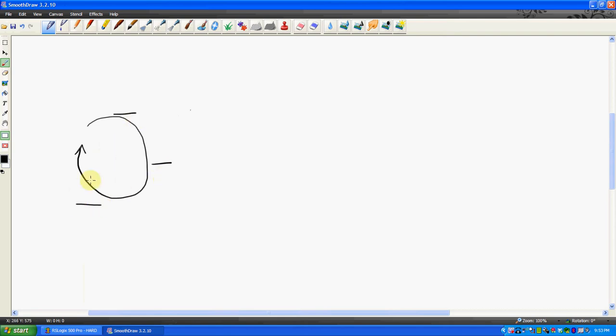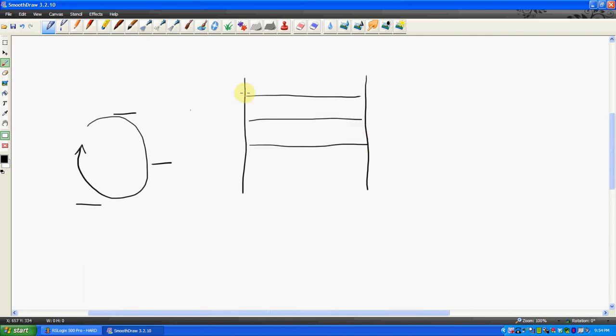It's sort of a bigger picture of what's happening in the whole PLC, but more to the important part of this video, ladder logic inside the PLC is always processed the same way. It's always processed the way we'd read a book, from top to bottom, left to right. So it reads across here. At the end of this line, it would now read this, and so on, working its way down the rungs. If left default, this is the scan cycle, left to right, top to bottom.